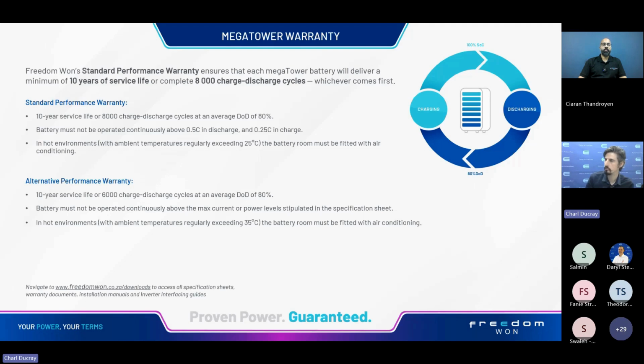For the megaTower, we max out at about 0.6 C. We do allow peaks for 1 minute of higher C rates, just to allow your loads to settle or for motor startups, and then it needs to settle back down to 0.6 C. Our technical team is well versed in sizing our megaTowers to meet any site demand.